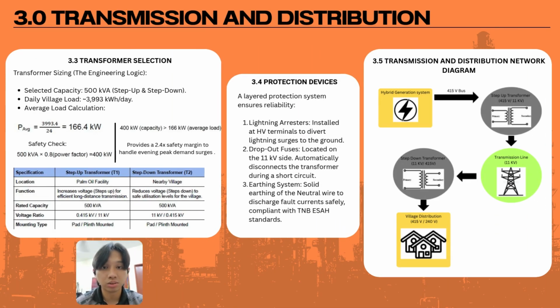Moving on to slide 2, that is transformer selection, which is the most critical part. We calculated the village daily energy usage, roughly 3,993 kilowatt-hour. When averaged over 24 hours, the continuous load is only 166 kilowatt. However, we select a 500 kilovolt-ampere transformer, which gives us 400 kilowatt of real power capacity. We choose this larger size to handle peak demand.